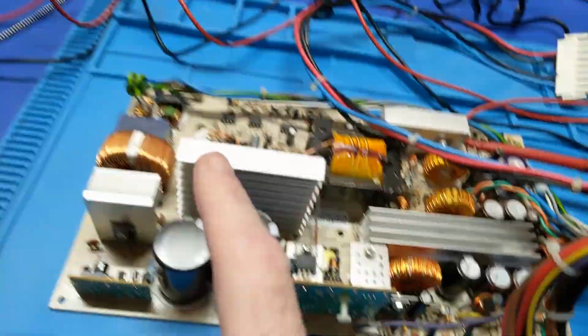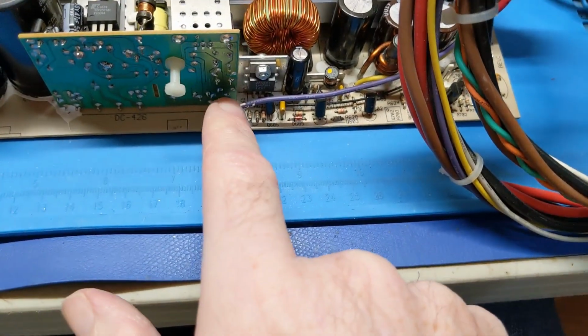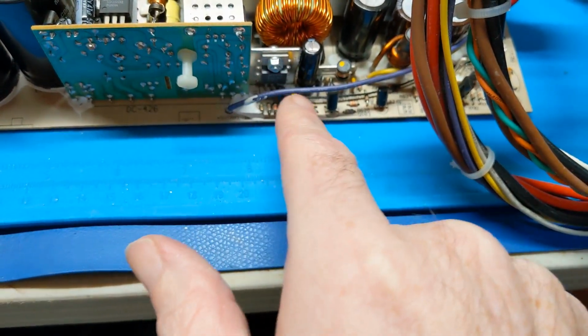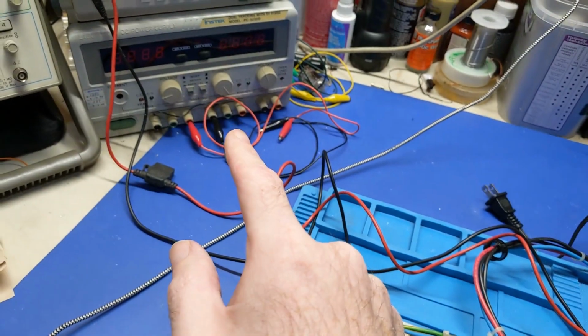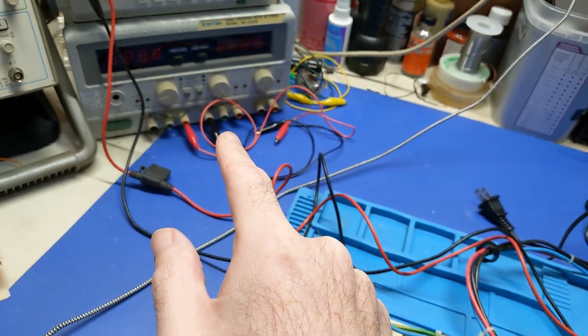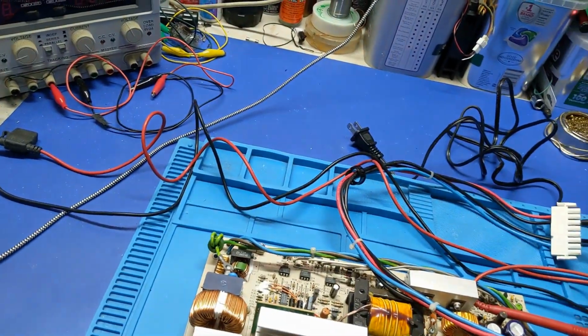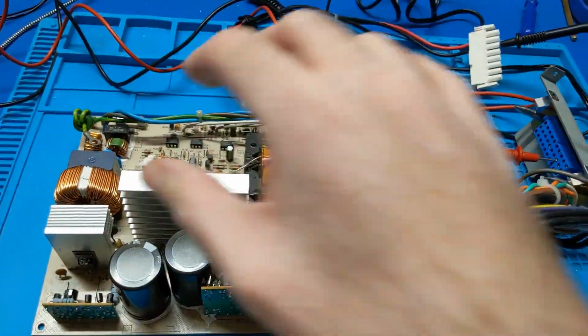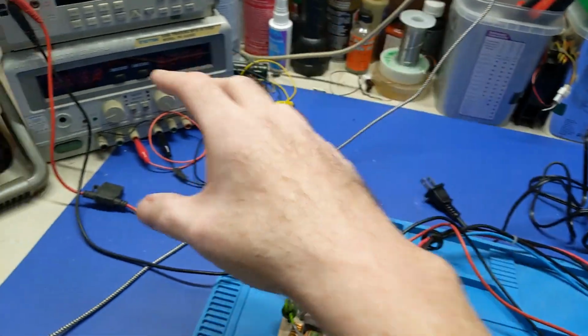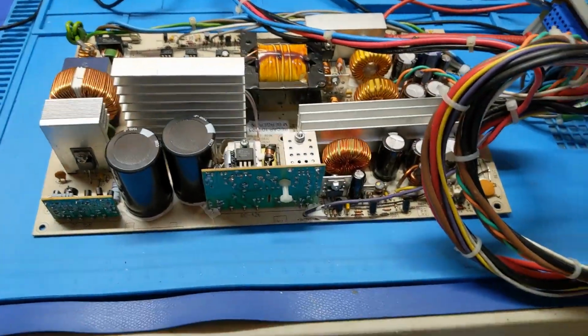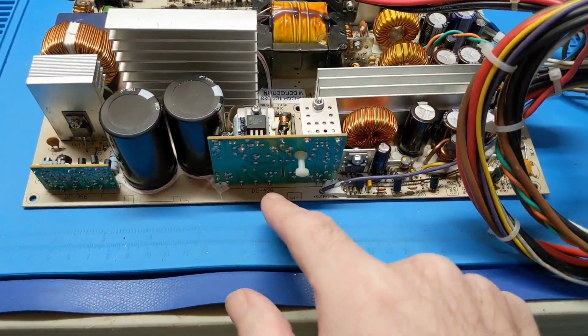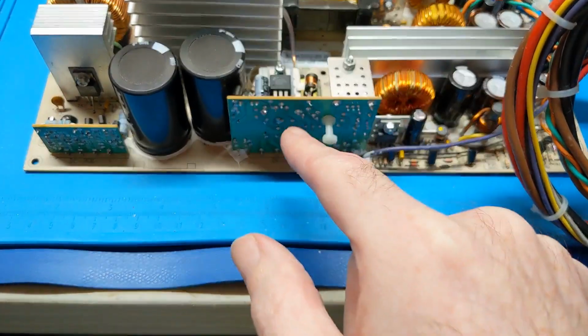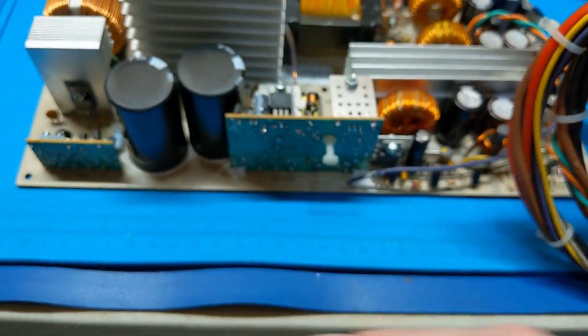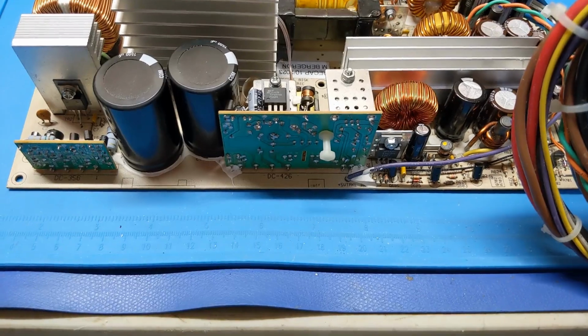Now what I could do is take this bench supply and feed 5 volts in here as well as 12 volts, because this has some other voltages that go out too. But that's not isolated, so that's dangerous. The hot and cold grounds are separate, so unless I have an isolation transformer, you can't do that. So I need to get in here with my probe and start checking primary voltages to make sure all of that is there, or it won't work.